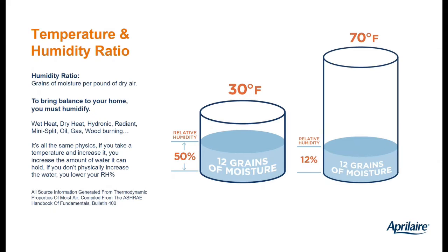In the first scenario, the air temperature is 30 degrees and there's 12 grains of moisture in the air. That's how we measure absolute humidity. So this is a typical outside day for much of the country during the heating season. The height of the cylinder represents how much moisture the air can hold. So at 30 degrees, the air can't hold a lot of moisture, so that cylinder is relatively short. The amount that the cylinder is filled represents how much moisture is actually in the air. And the ratio there, you can see that cylinder is about half full, so the relative humidity is 50%. It's halfway towards being saturated with moisture.